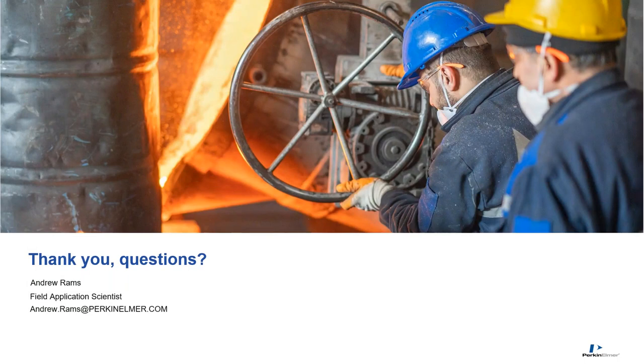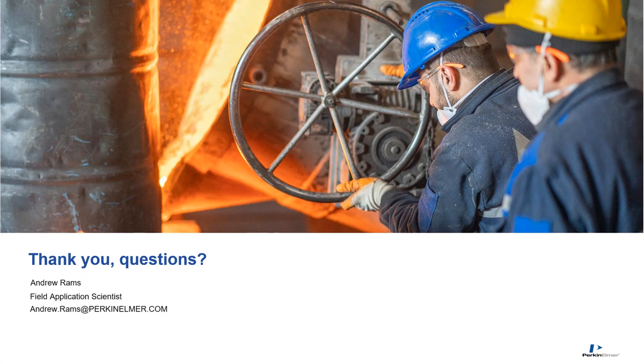One question: how long does the average reading of a CRM take in the rare earth method? For that method, it wasn't just REE — it was a lot of the base metals and many other elements in the periodic table since those CRMs were qualified for a lot of different elements. That method was completed in just over four minutes — about four minutes and three or four seconds. There were probably upwards of 85 to 90 isotopes being measured across eight gas modes. That's pretty good: just over four minutes for 85-90 isotopes across multiple modes.